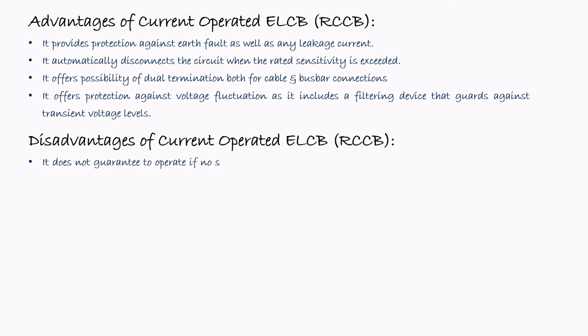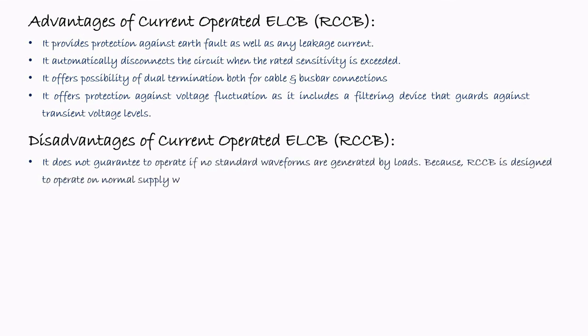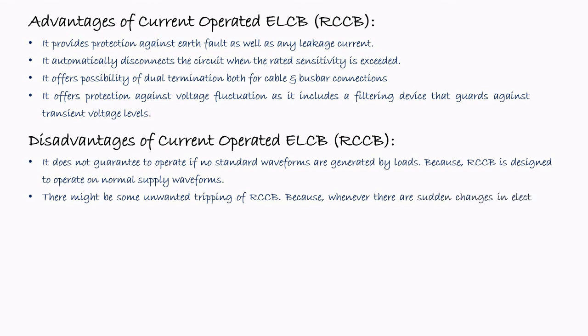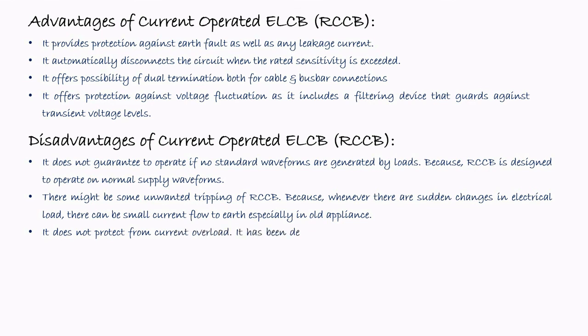Now some disadvantages. It does not guarantee to operate if no standard waveform is generated by the load, because RCCB is designed to operate on normal supply waveforms. There might be some unwanted tripping of RCCB because whenever there are sudden changes in electrical load, there can be a small current flow to the earth, especially in old appliances. So in that case, the RCCB will trip. It does not protect against current overload. It has been designed to protect only when the live current and the neutral current are different. That means if there is any leakage in the system, then only this current operated ELCB will activate. For normal overload condition or short circuit condition, ELCB will not operate.